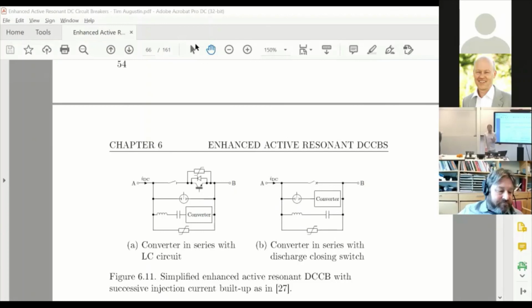And then when the commutation can be initialized and how long the arc has to burn in the mechanical contact, that is a different question. One could, for instance, try to commutate very early on, just when the metal bridge is forming and when it has exploded, so that one tries to avoid too much heat buildup in the contact gap.